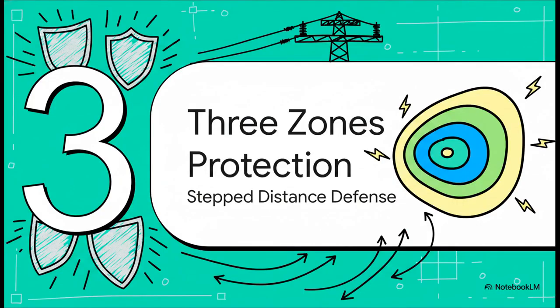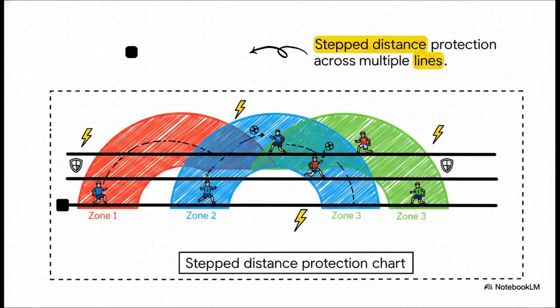Section 3. The 3 zones of protection. So now that our relay knows how to spot a fault geometrically, we need to talk strategy, because you never ever want to rely on just a single line of defense. Engineers developed a brilliant system of overlapping coverage called stepped distance protection.